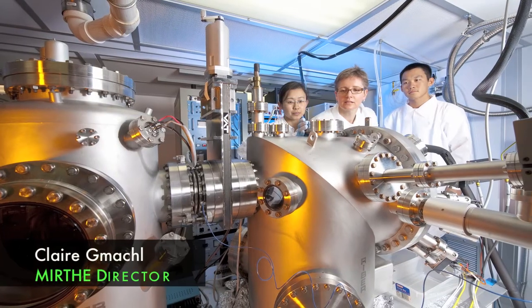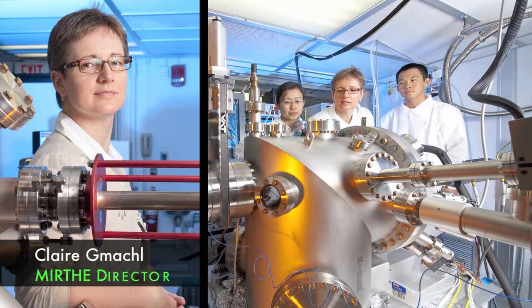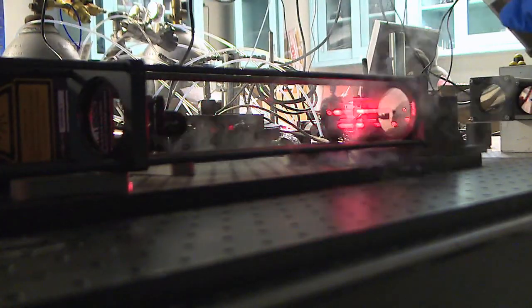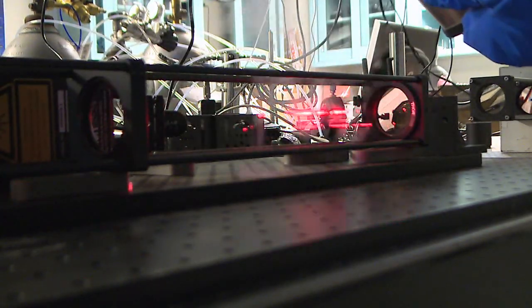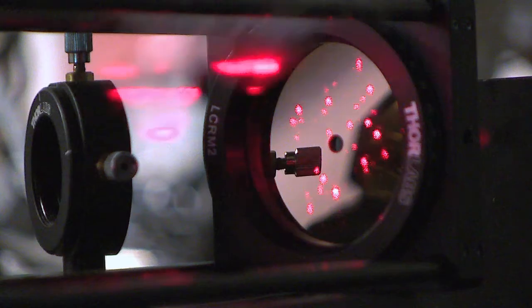MIRTHE and its director, Professor Claire Gmachl, were extremely supportive of us. We design and engineer our sensors so that the laser can trace out a long path to increase the sensitivity of our measurements. To do this, we bounce the laser many times between two mirrors, which is known as a multi-pass optical cell.